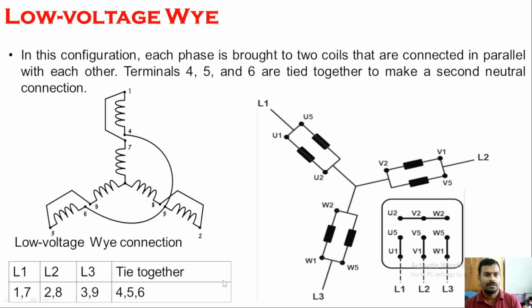And now let us see low voltage star connection. In low voltage star connection, 2 coils of each star connected phase will be connected in parallel. So the current coming from here will get divided into these 2 coils. So the current can be higher, and the voltage across these coils will be lesser. So this is a low voltage, high current configuration. It is connected in star connection.